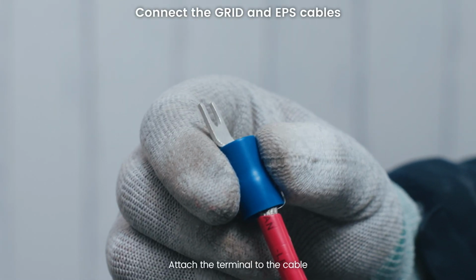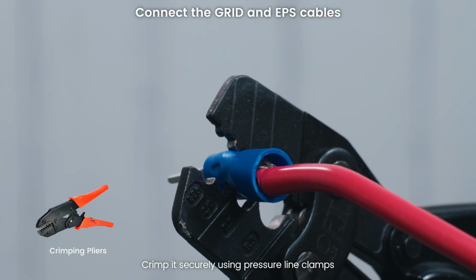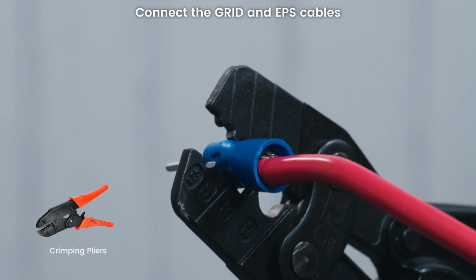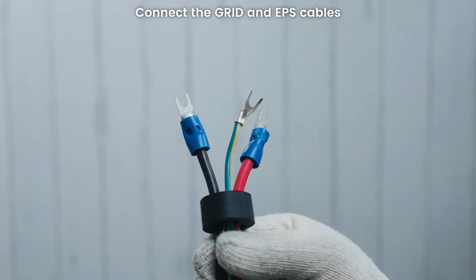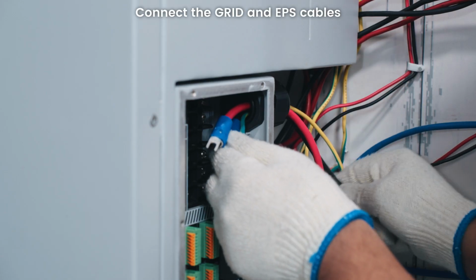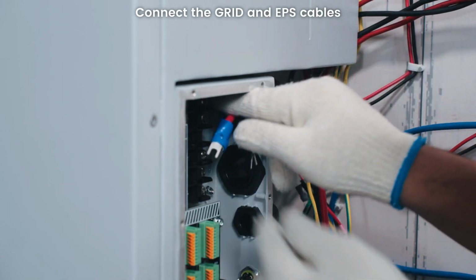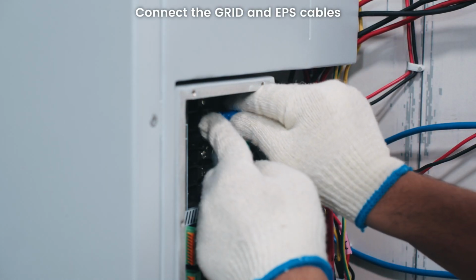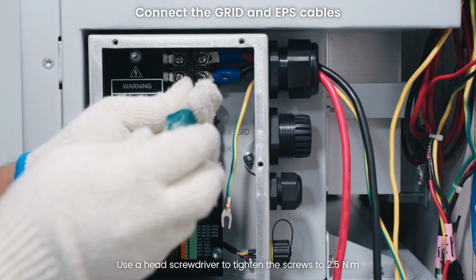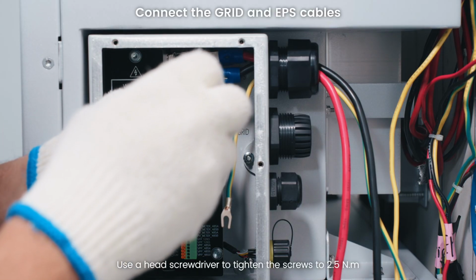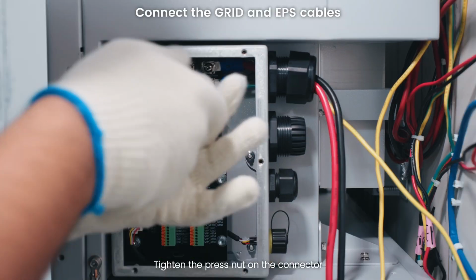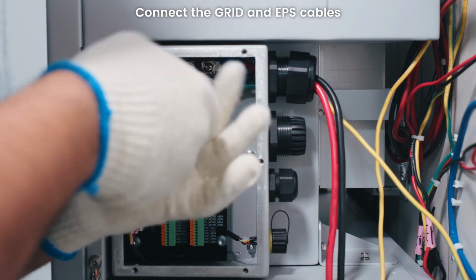Attach the terminal to the cable. Crimp it securely using crimping pliers. Use a screwdriver to tighten the screw to 2.5 N.M. Tighten the press nut on the connector.